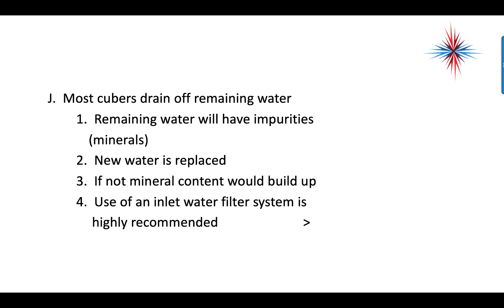Most cubers, upon completion of the cycle, drain off the remaining water in what we call a waste or drain cycle. The remaining water has a lot of impurities, like the minerals. Once that's drained, new water replaces it. If not, mineral content would build up. Use of an inlet water filter system is highly recommended. Just a side note on this - if you do not have a good drain, you will find that people will have water all over floors. Check that drain line and make sure that the drain actually works and is drained to an appropriate spot.